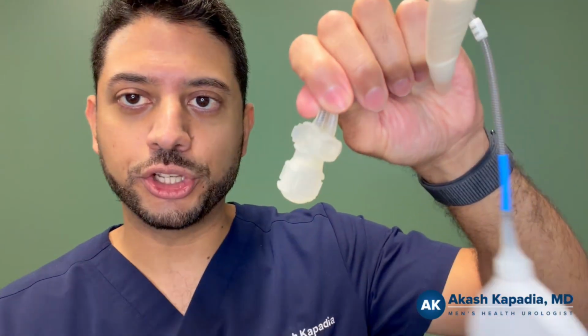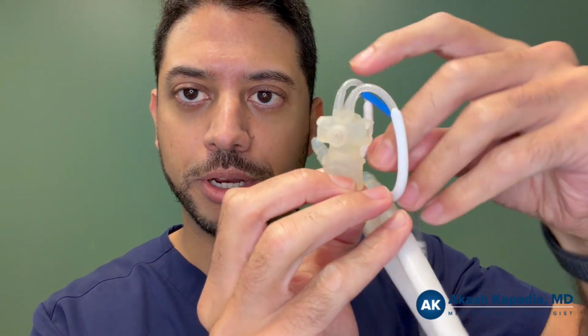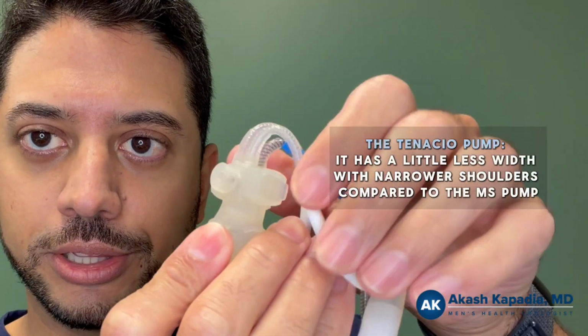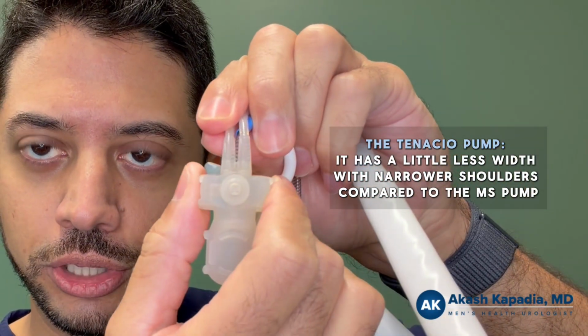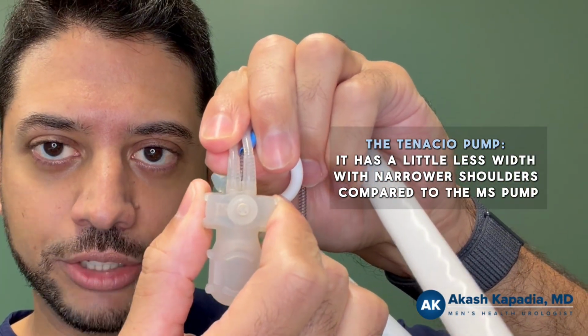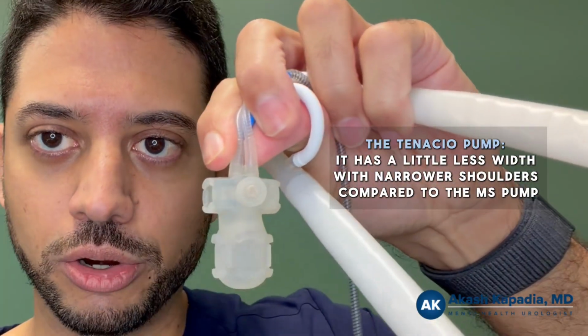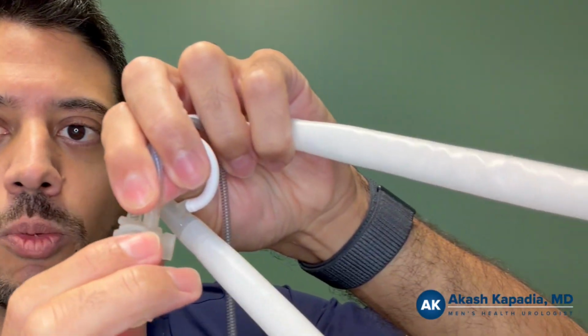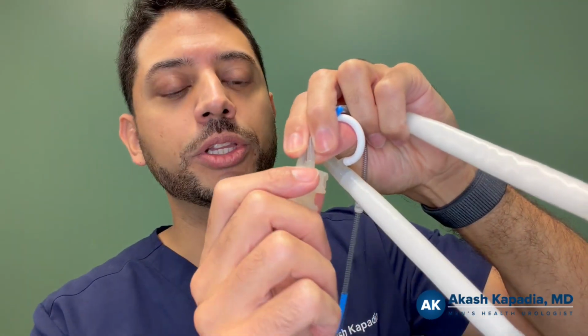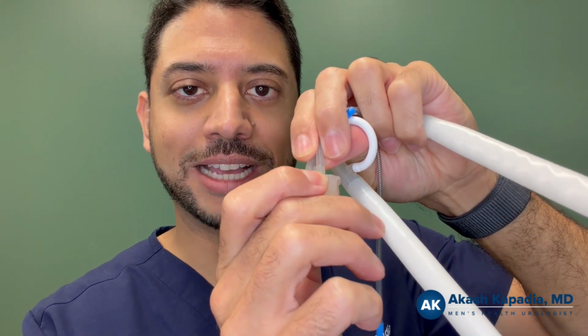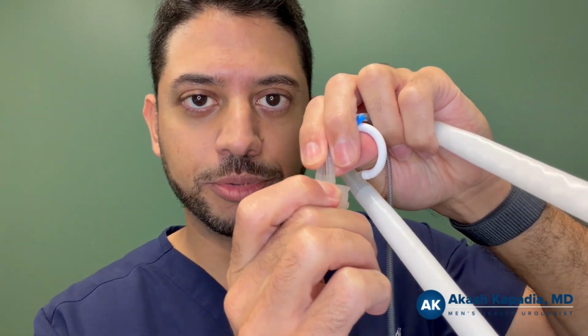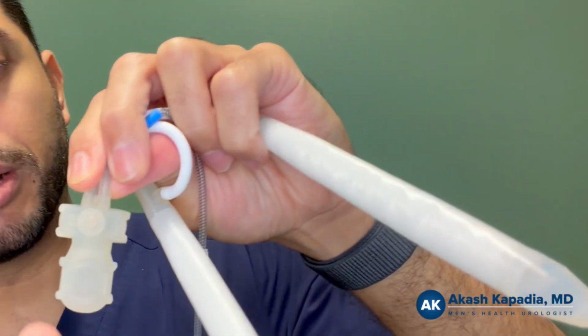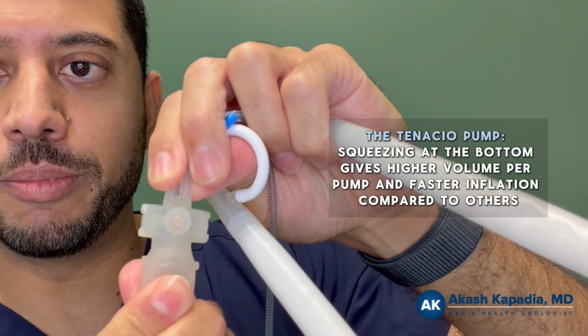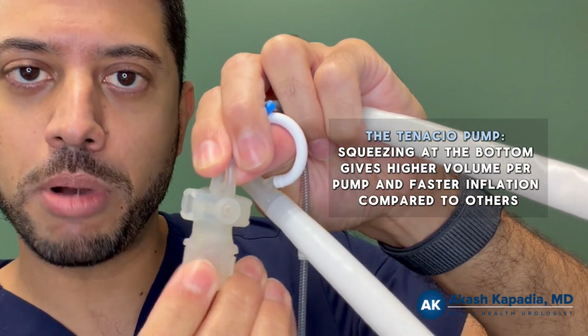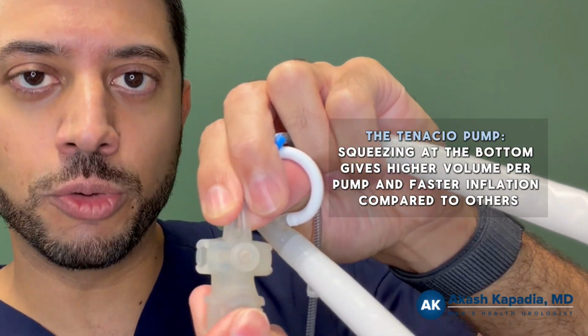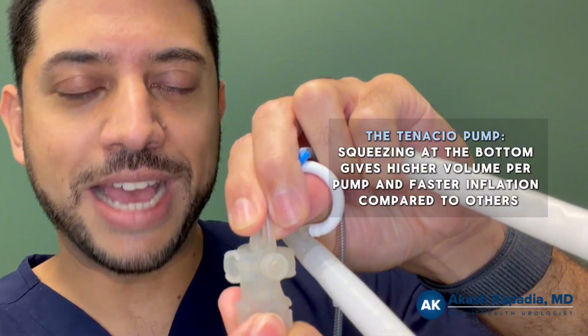So this is the Tenacio pump. What you might appreciate right away is that it has a little less width. The shoulders are a bit narrower compared to the MS, but it's a little longer than the MS pump, and maybe a little wider in this aspect. One thing we lose with this pump is that haptic feedback, the vibration we're accustomed to with the MS touch. What you gain with this pump is the ability to squeeze down at the bottom rather than in the middle part of the pump, to get a higher volume per pump and a faster inflation.